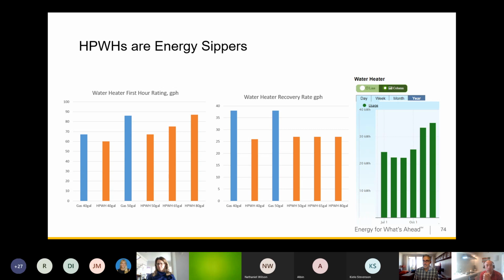But I will tell you that the 50-gallon heat pump water heater we installed for our ADU for the couple living there has been more than adequate, not a single issue with supplying a couple. And you can see on the right, the amount of electricity it's using is on average less than 1 kilowatt hour a day. Really efficient. And you've got the electric resistance heaters locked out as well. Correct? That's right. But I haven't done anything like locking it out during 4 to 9 p.m. because these are my tenants. I don't want to put them out. It's just running in heat pump mode all the time. All the time. I see it turn on about twice a day.